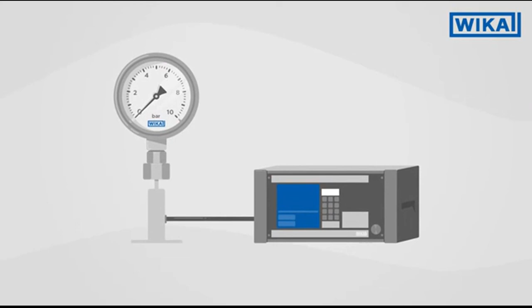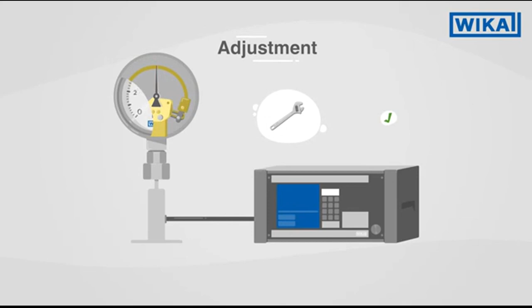If the deviation of the calibration item is within the manufacturer's specifications, the calibration certificate will be issued with a specific confirmation. If the deviation is too large, the instrument will be reset. This process is known as adjustment. It can then easily be used again. A special case of calibration is represented by verification. Here, the calibration process is certified by a government agency. This is required in some cases, for example, for the purpose of consumer protection. In our Wika laboratories, we are able to calibrate as well as adjust and verify your measuring instruments. We are happy to answer any questions on calibration services.